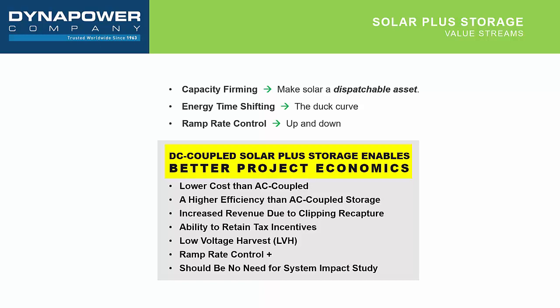But these are all things that you can do with either an AC coupled or a DC coupled system, or hybrid for that matter. So what are the things that you can now do, or what are the advantages of going to a DC coupled configuration? Well, and we'll go through each one of these in a bit more detail, but to summarize, you have a lower balance of plant cost, DC coupled, than you do with an AC coupled system. You have a higher round trip efficiency when you're cycling the batteries. There's increased revenue opportunity by virtue of clipping recapture.